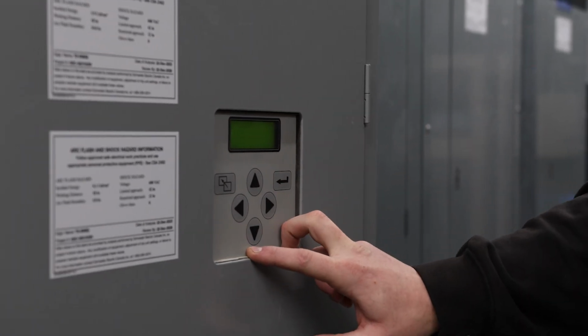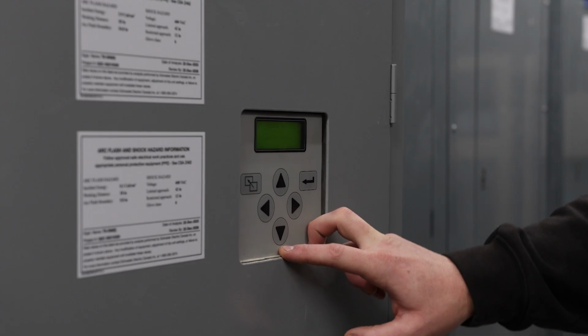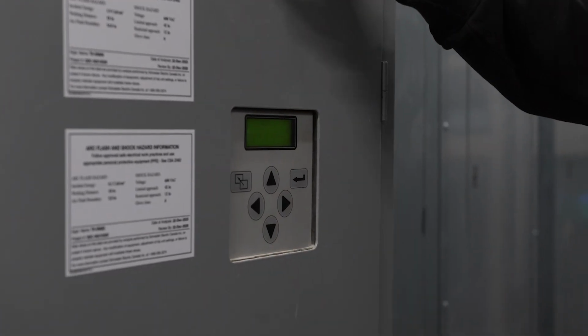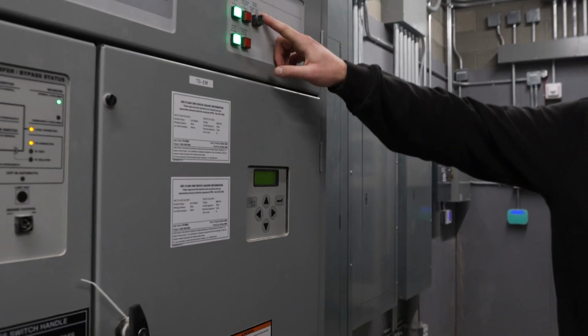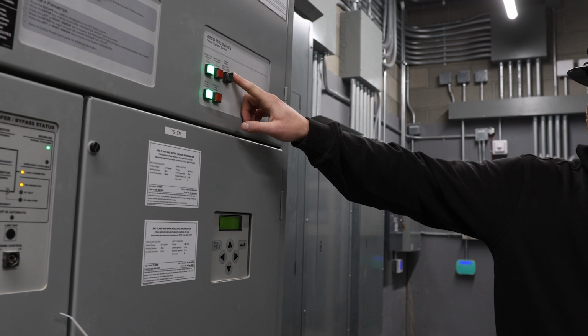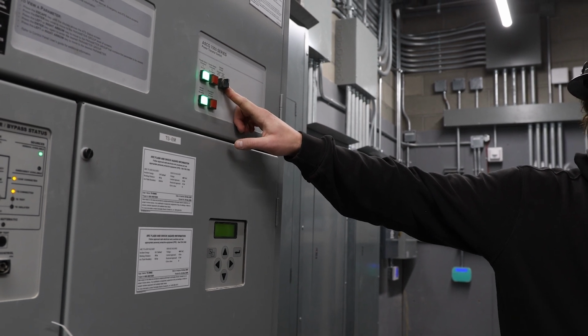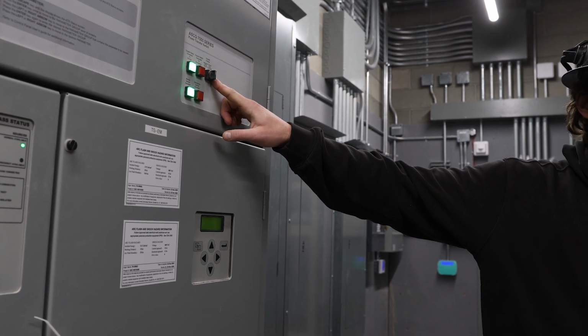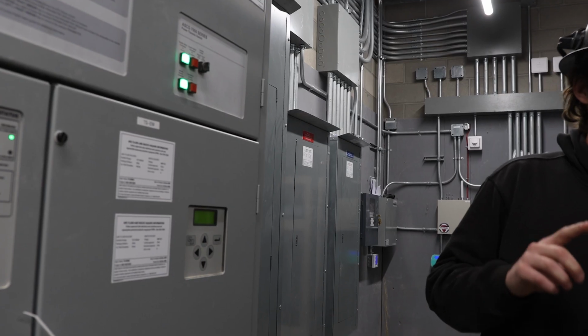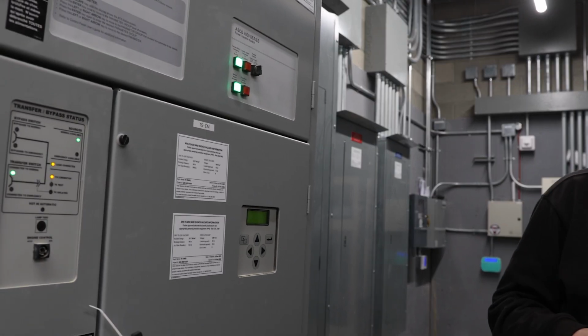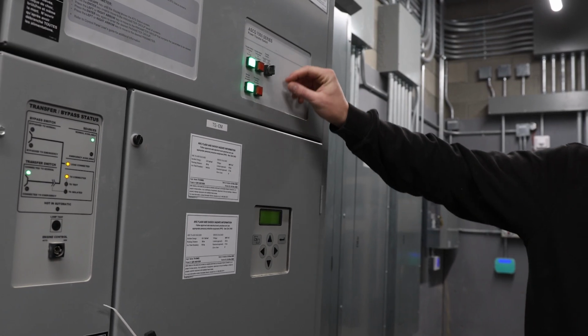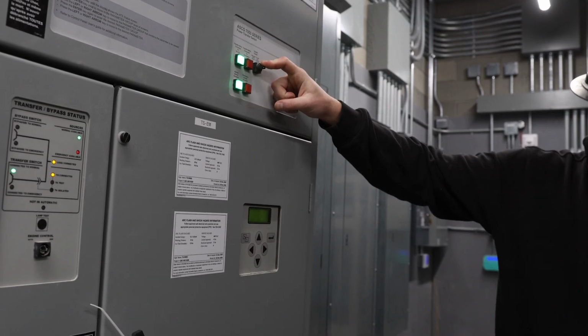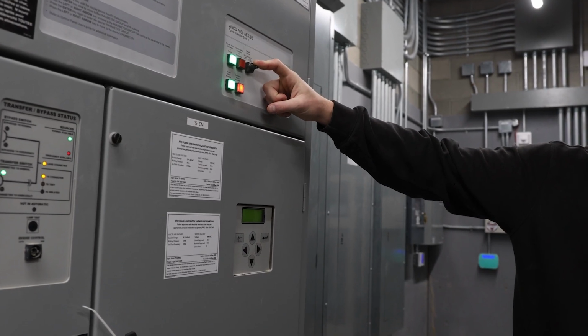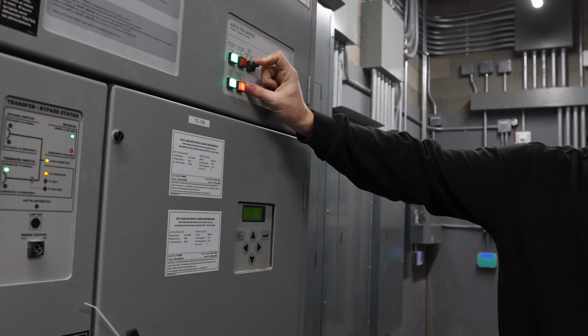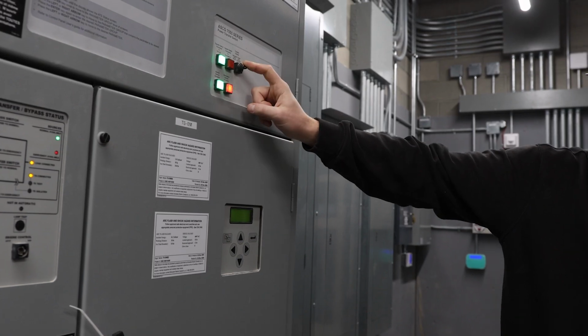What you'll do with the transfer switch on your monthly testing is, up at the top, we have a knob. Transfer control is what the knob is called. Turning it to the right and holding it for approximately 15 seconds, it will start and begin the transfer sequence for the generator. So we'll go through that right now. On our display, it's showing that we're in test mode. Our generator has started. We're seeing source accepted, and release that.